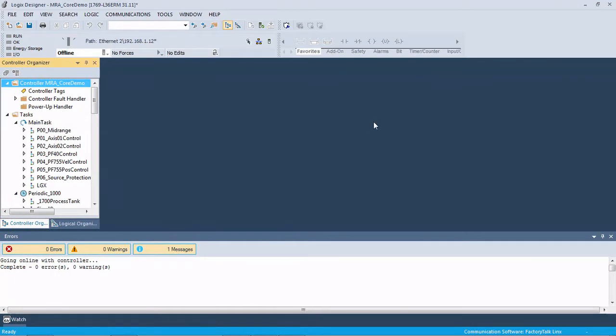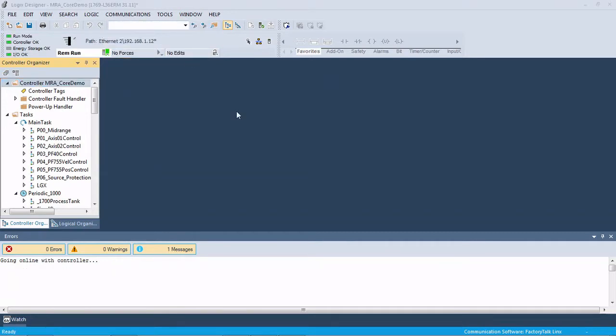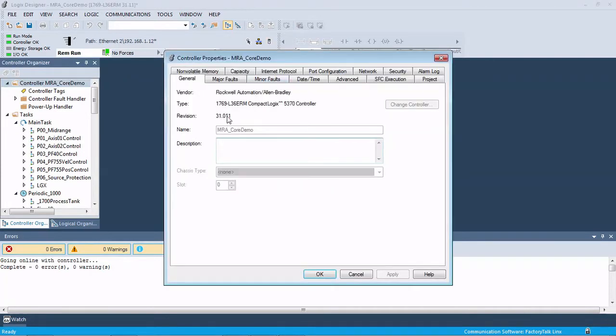All right. So here we are back at our program. The lights on my processor, the run light has come on. The IO light's solid. That indicates to me everything's back up and running, as well as the panel view I have connected here is back up and talking to the processor. So I know it's good. And I can just come in here, go click, go online just to verify. And so what happened was the firmware got updated on the processor. The program got loaded and the IP address changes, the settings were all reset to what they would have been when it was saved to the SD card.